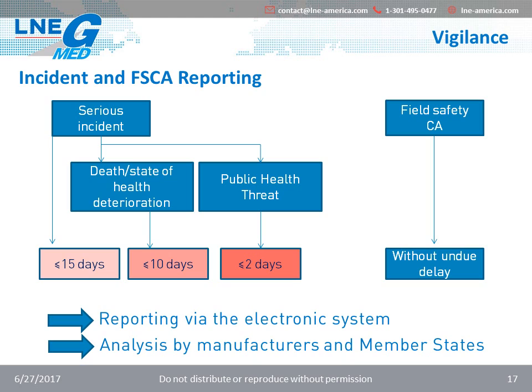The manufacturer shall take into account the severity of the serious incident to determine the time frame for reporting it. Based on the severity of the incident, 3 different time frames have been defined: 2, 10, or 15 days. Both regulations give more detail on each situation. All reporting to relevant competent authorities shall be done using the Eudamed electronic system and data analyzed by both the manufacturer and the member states.